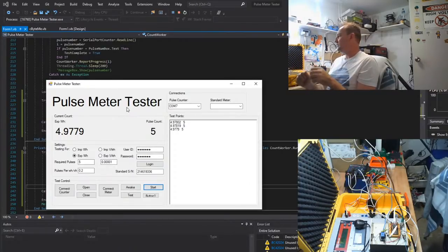When you turn the device off, that energy gets returned back to the network. So that's why you never pay for your VAR hours, and you'll know what I'm talking about, because if you have a digital meter, you'll see you've got 2 LEDs. One flashes on VARs, one flashes on watt hours. So that's why they're both there.